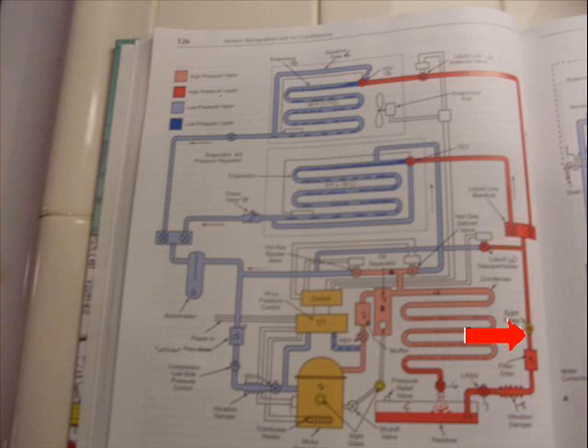Now, sight glass. Sight glass is a viewing device. It can tell us three functions. Number one, if there is a moisture indicator in it, the moisture indicator will tell us if we have moisture in the system. Generally, green is good. The system is dry, has no moisture. Yellow means that the system has got moisture in it. A brown color indicates there was a burnout and the acid has destroyed the crystals and the tech was too lazy to replace the moisture indicator by replacing the sight glass.